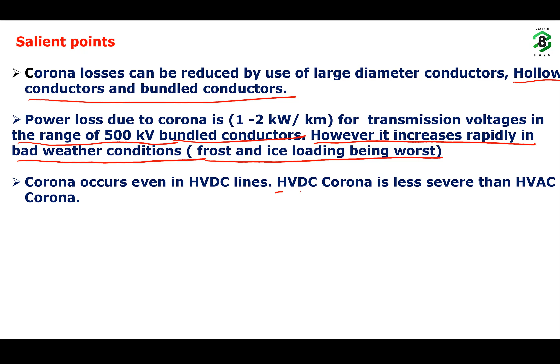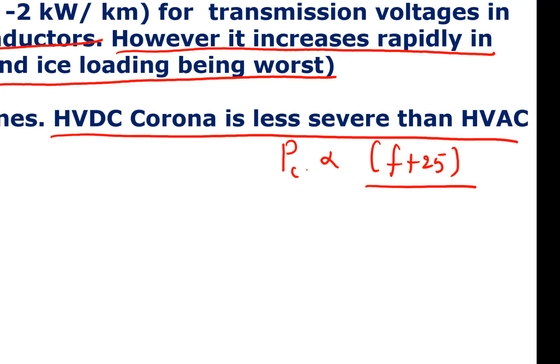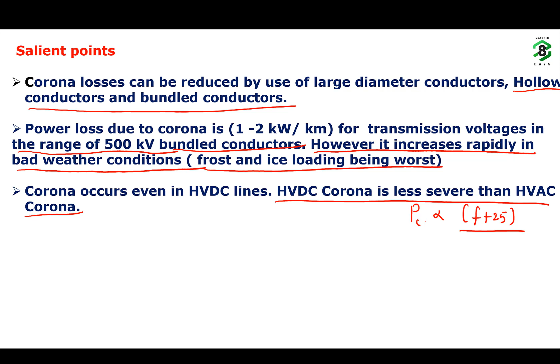Corona even occurs in HVDC lines, but the HVDC corona is less severe than HVAC corona. Why? Because we have already seen the corona loss is directly proportional to (f + 25). So in HVDC, the frequency is 0, so the corona loss is also less. The corona in DC lines is smaller when compared to the corona in AC lines.